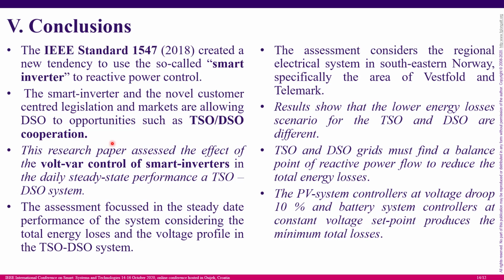Conclusions. Well, in this scientific paper, we take advantage of the IEEE Standard 1547 from 2018, and we are using the concept of a smart inverter. And in this case, we are exploring the interaction between the transmission system operator and the DSO, considering several Volt-Var controls used for the smart inverters. The interesting thing here is that active energy losses in the TSO and DSO are antagonistic. I mean, when you try to reduce them in one area, the other area increases, and likewise. For that reason, the TSO and DSO must find a balance in the reactive power flow to reduce the energy losses. And that is where the integrated and communicated interaction between the TSO and DSO takes place.